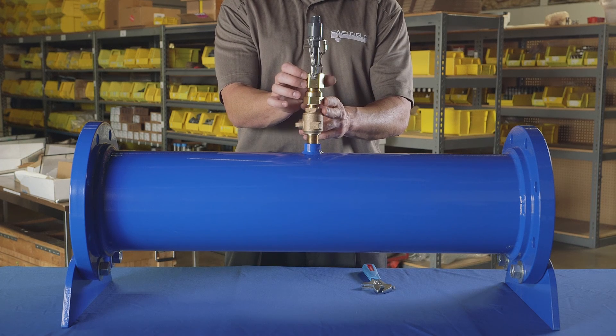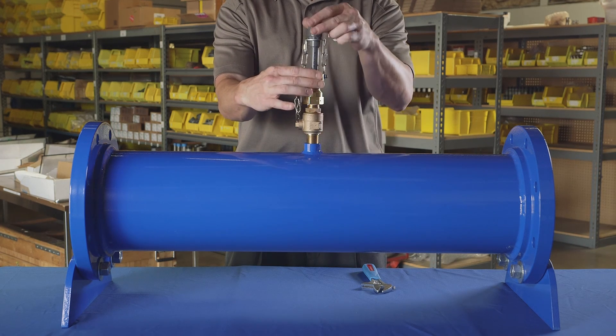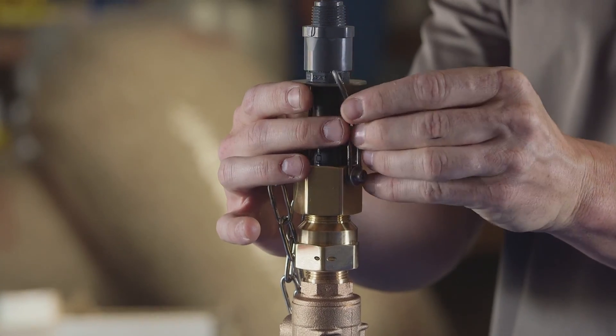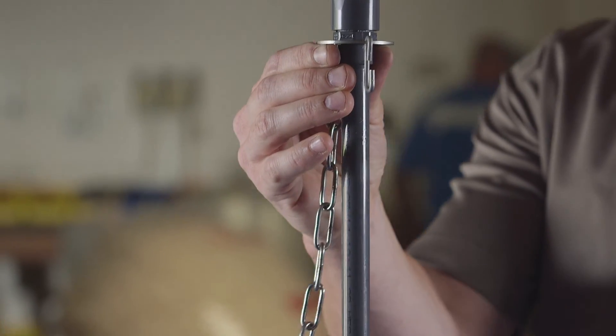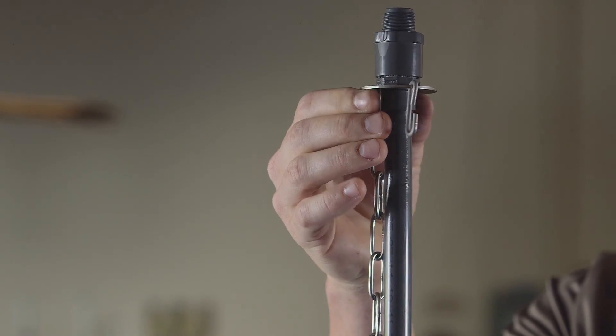Start by turning the packing nut counterclockwise, just enough to allow the solution tube to be pushed in towards the pipe. Continue pushing the solution tube towards the pipe to release the hook from the restraint chain. Allow the solution tube to slide out from the main connection until the limit chain is completely extended.